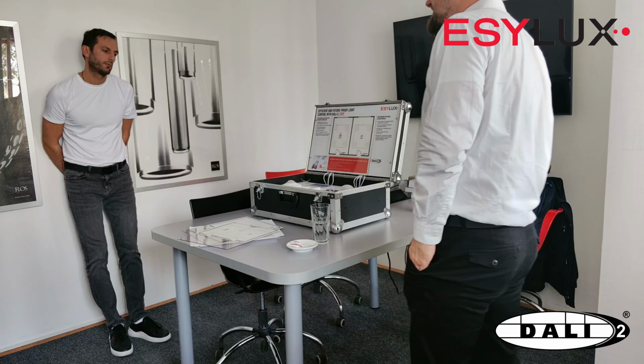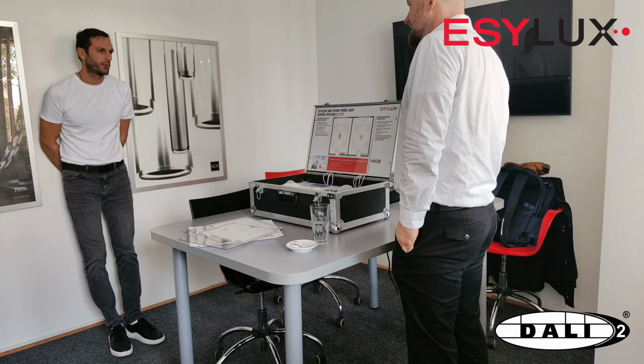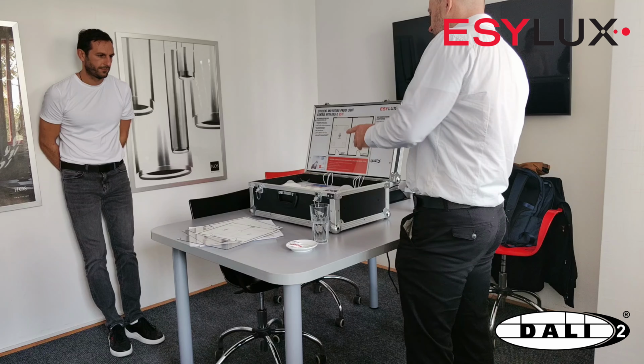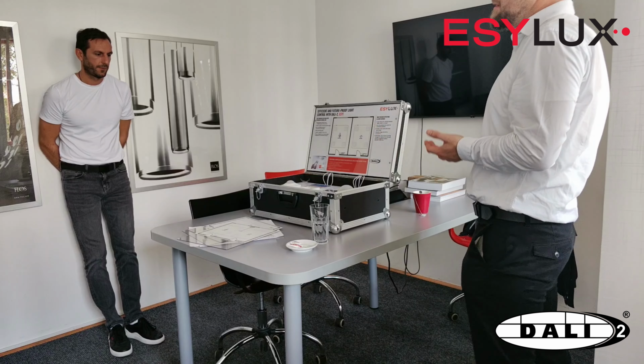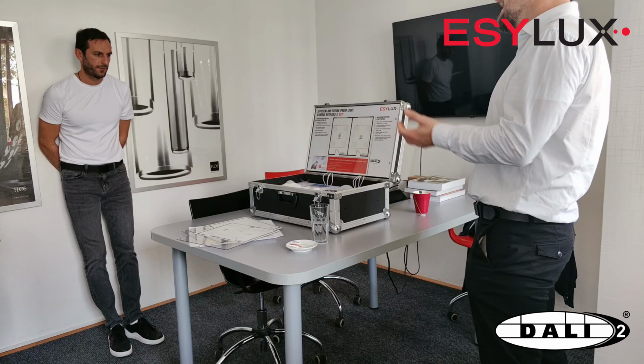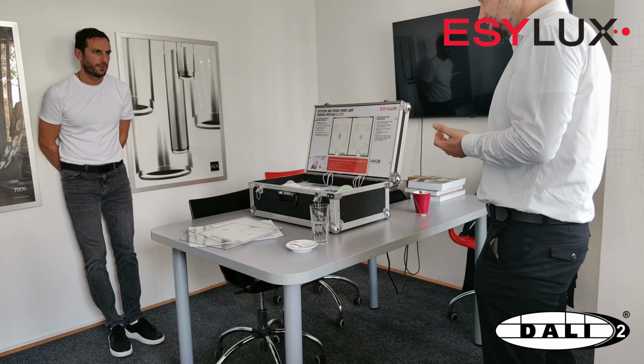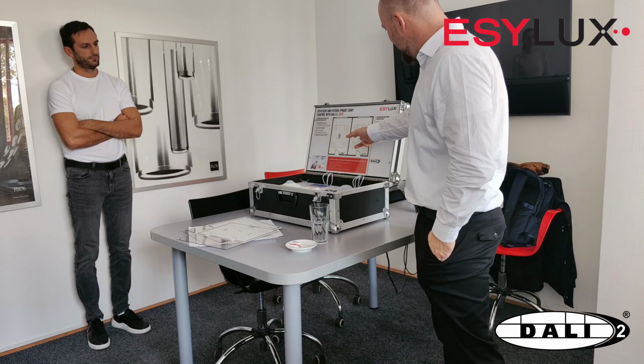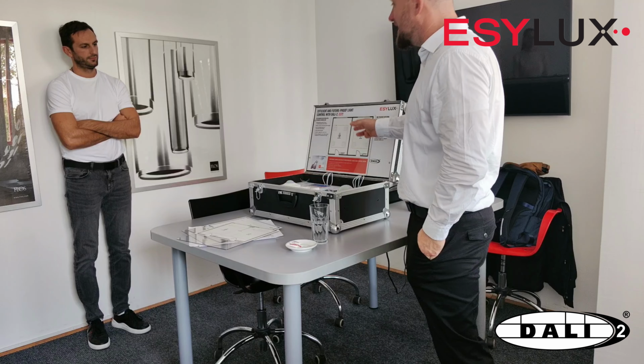The limitation normally is 64 input devices, but the limitation of the DALI bus current consumption comes first. But now you also have the possibility to use, for example, a DALI-2 repeater, which lets you increase the DALI bus, and you can also include DALI-2 actuators.